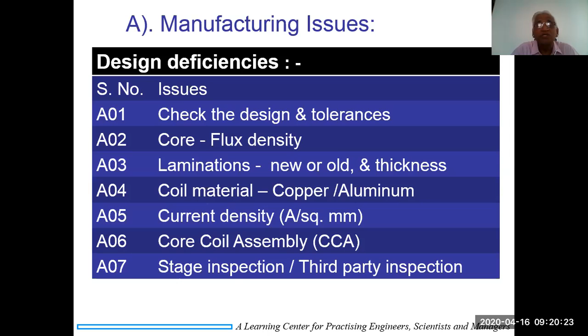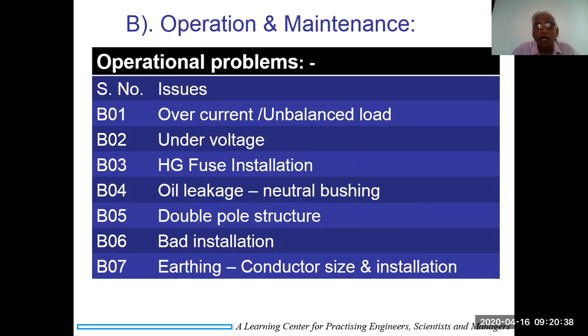practices. Now, if we look at it, manufacturing issues: checking the design of tolerances, core flux density, laminations, new or old, and their thickness, coil material, copper and aluminum, current density in amperes per square millimeter, core coil assembly, and stage inspection or third-party inspection. Operation and maintenance issues will be overcurrent, unbalanced load, undervoltage, HG fuse installation, oil leakage and neutral bushing, double pole structure and bad installation, and earth conductor size and installation.